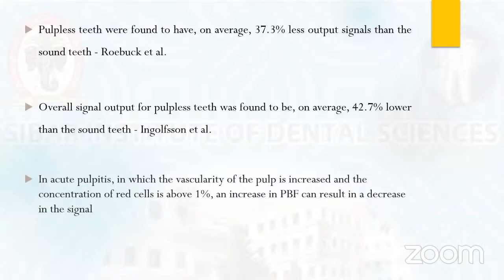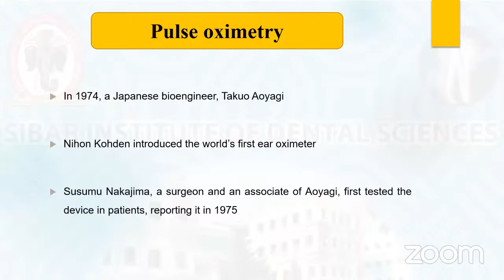Pulse oximetry: again, these are Japanese researchers, and it is based on Beer's law and Lambert's law. Beer's law says the absorption of light is proportional to the concentration of the sample, so what we are measuring here is oxyhemoglobin. Lambert's law says that the absorption is proportional to the thickness of the sample, and we can use this in pulse oximetry.